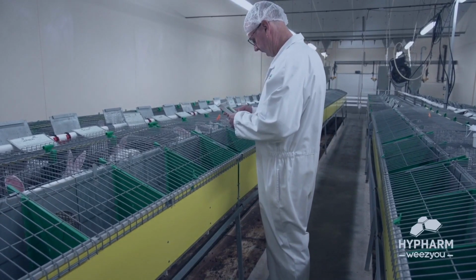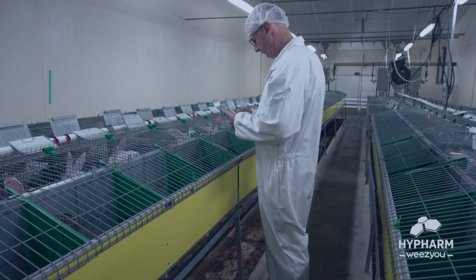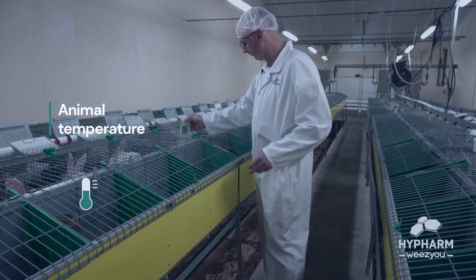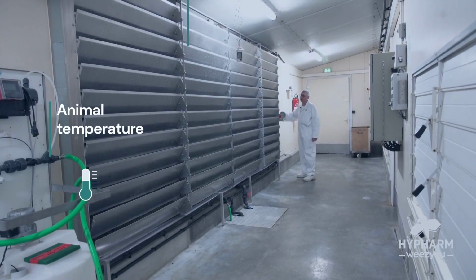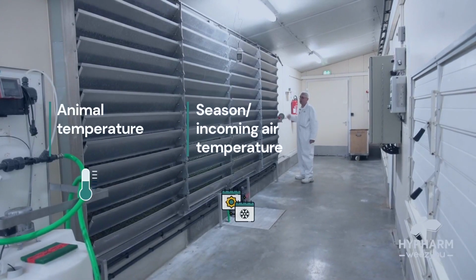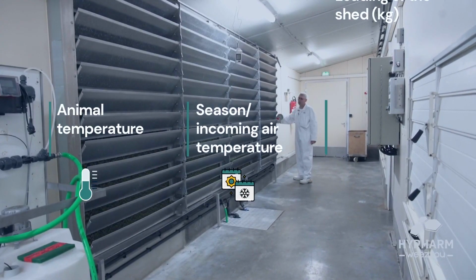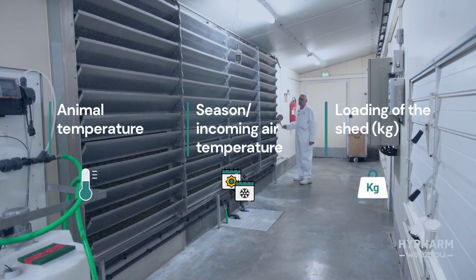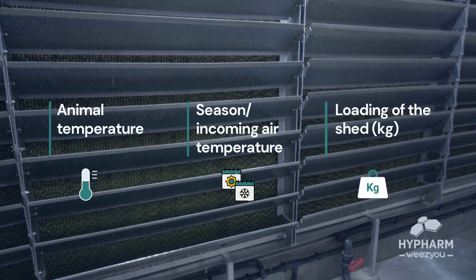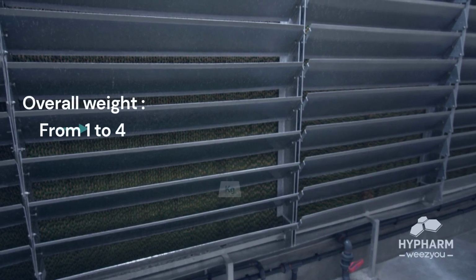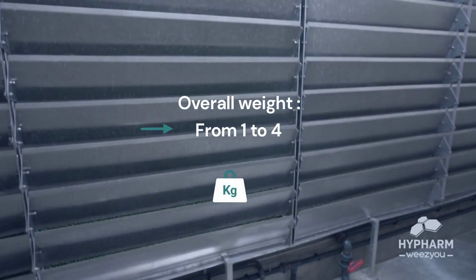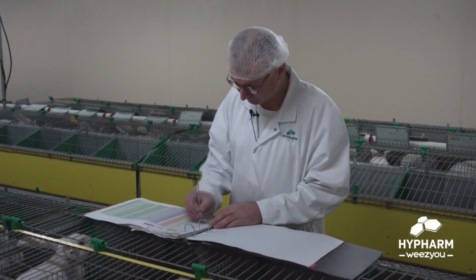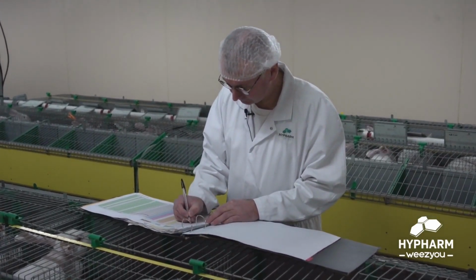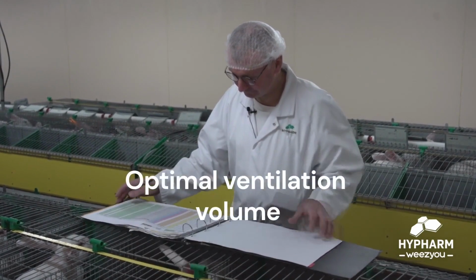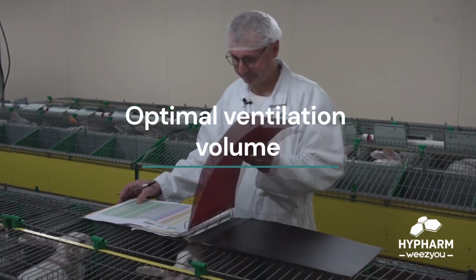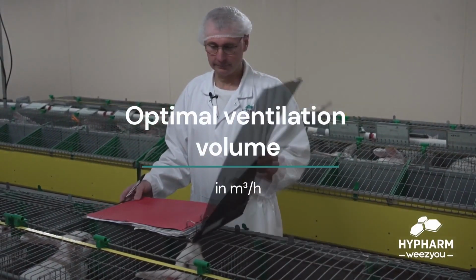To ensure this, the following elements need to be considered: the temperature at the height of the animals, the temperature of the air entering the rearing shed and the season, the loading of the shed expressed in kilograms of animals. Remember that for all-in all-out systems, this loading increases from 1 to 4 during the production cycle. So using this information, we will estimate for each period and for each batch the optimal ventilation volume necessary for the animals, expressed in cubic meters per hour.